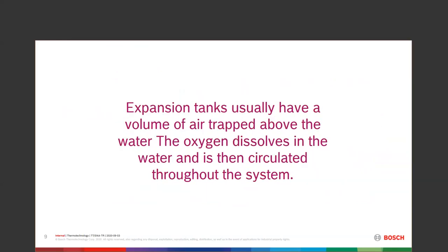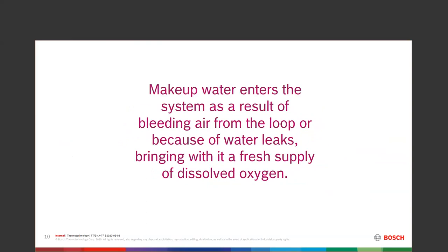Expansion tanks have a volume of air trapped above the water — whether a bladder-type tank or a direct air-to-water tank. That oxygen can actually get through the rubber membrane of the bladder and come out into the water. As we heat it, those little bubbles get big, we get noise and corrosion through oxidation. When we bleed air from a loop or have a small leak, we bring in a fresh supply of dissolved oxygen. We've got to get rid of that or maintain the system so we don't have to constantly address it.